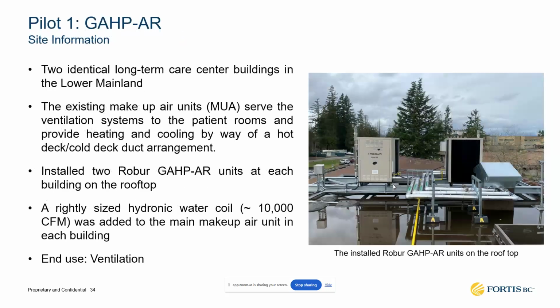Now, I'm going to show you a couple of case studies for gas heat pumps that we installed in the past. This is a long-term care center in a building in the Lower Mainland that had a large air handling unit, a 100% outdoor air unit, a multi-zone air handling unit that serves part of the building. There are two air handling units. One serves the north and the other one serves the south wing, if I remember correctly. So what we did is we installed these two gas heat pumps, and then we resized the heating coil of the hot deck to be able to accommodate the 60 degrees C from the Robur.